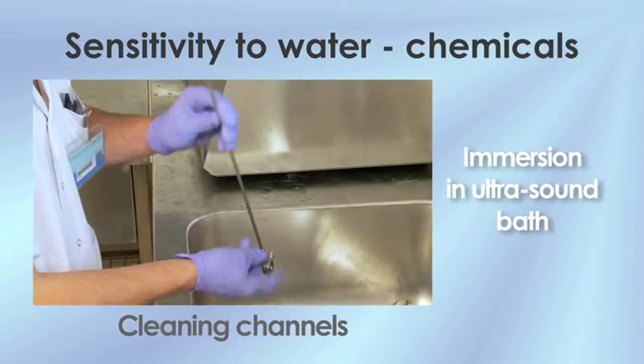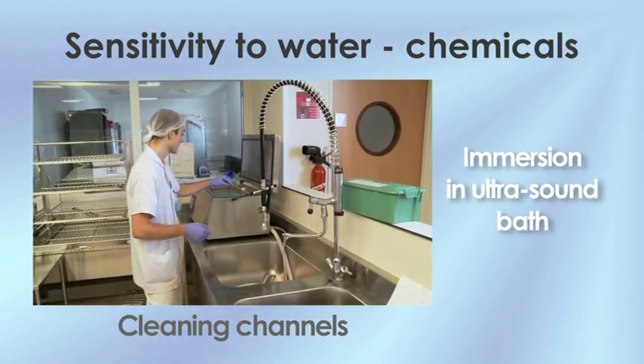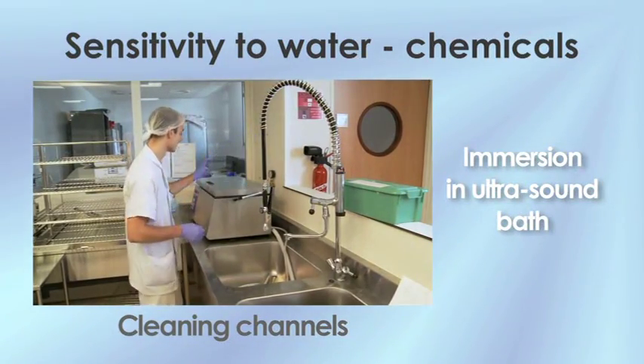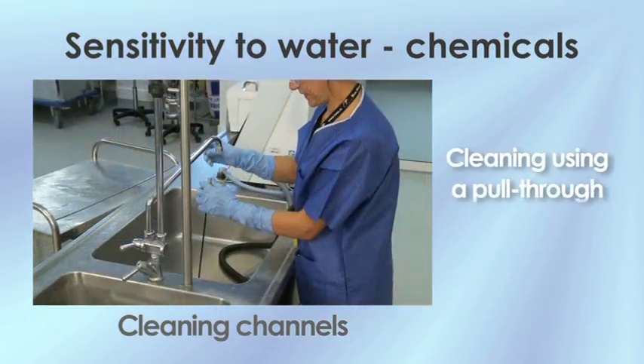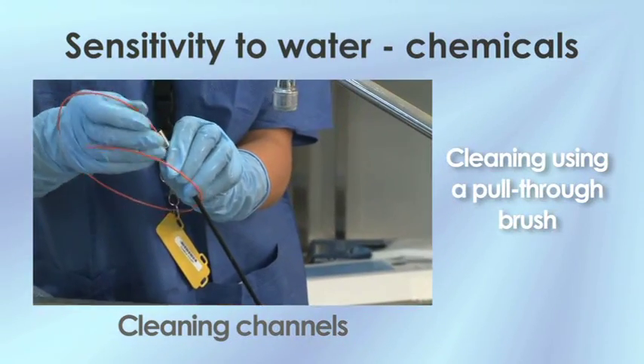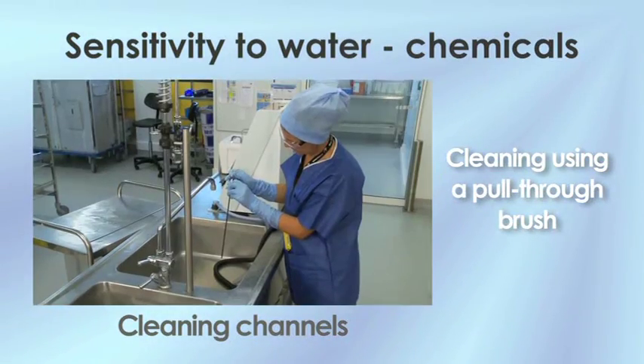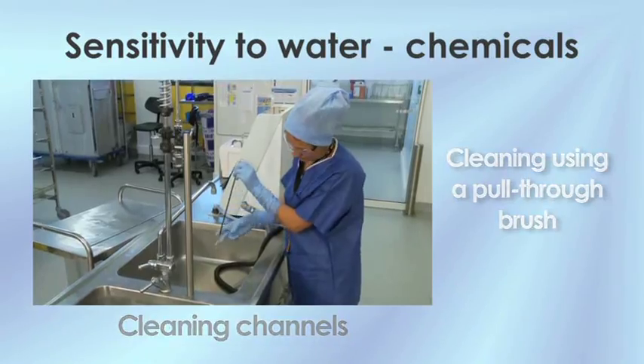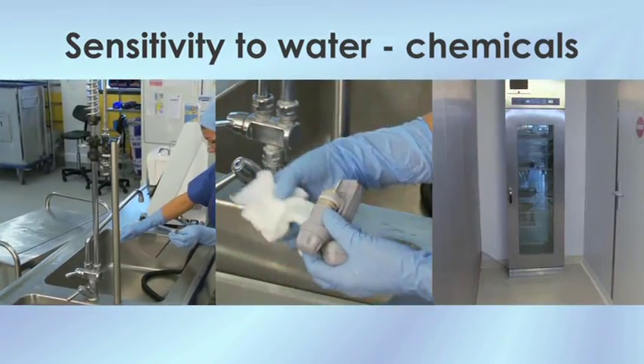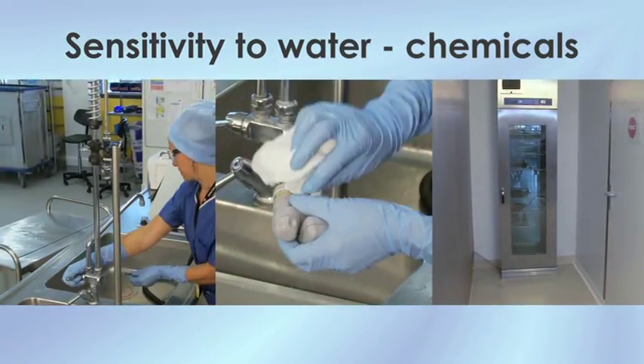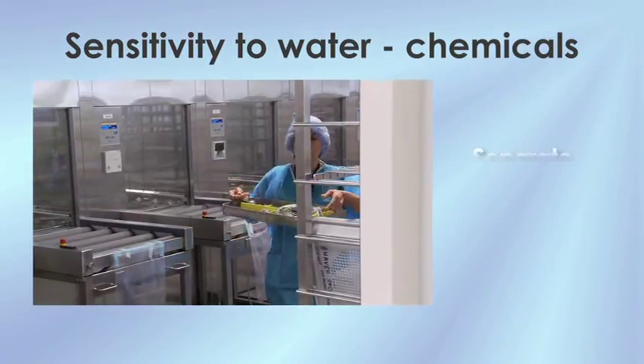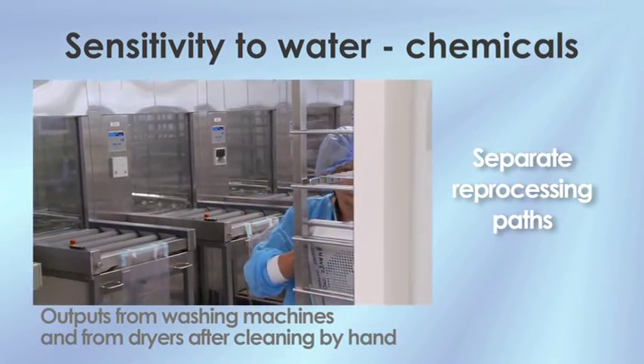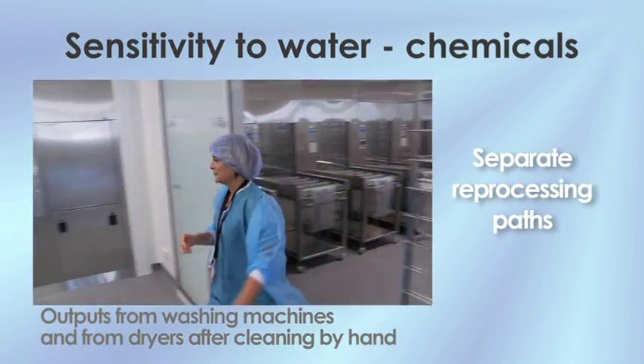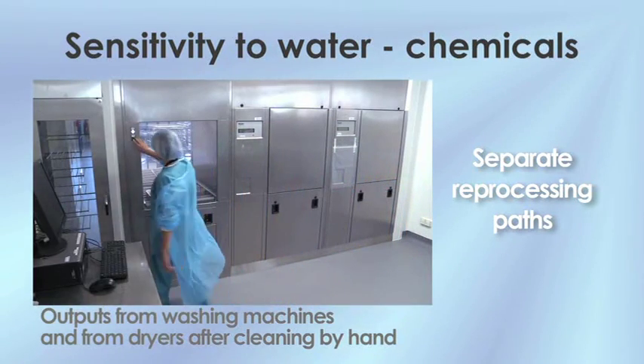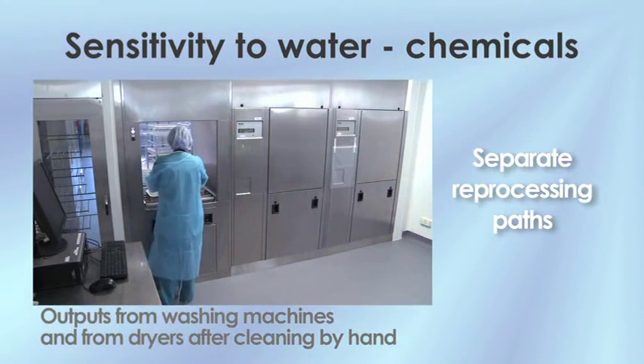Before being put in a washing machine, the devices need to be immersed in an ultrasound bath to dislodge any dirt in the channels and then cleaned carefully using a pull-through brush. All these operations extend the time taken by the technicians to clean each MD. When all the items in a given set require different cleaning processes, great care has to be taken to ensure that the sets are reassembled correctly.